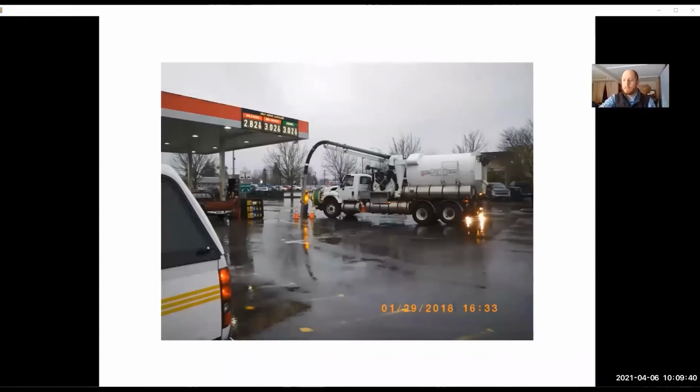This first example is a fuel spill on private property. We received a call from 911 dispatch about this fuel spill. In this case, our IDDE specialist arrived on site and found that the property was sloped in such a way that all of the fuel was directed to CBs that were flowing to oil water separators that were connected to sanitary sewer. He checked all the other CBs in the area for sheen and odor, as well as downstream at the storm pond to verify this.